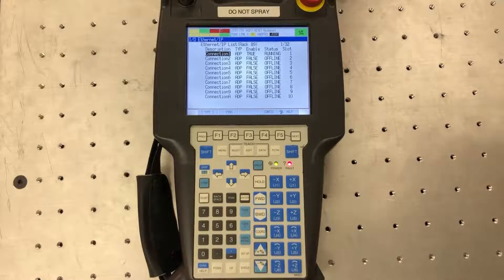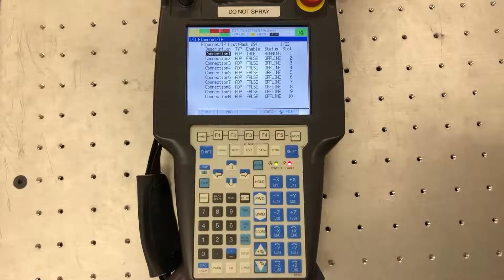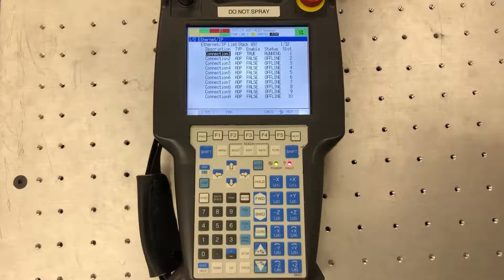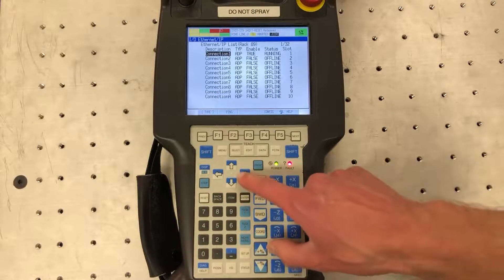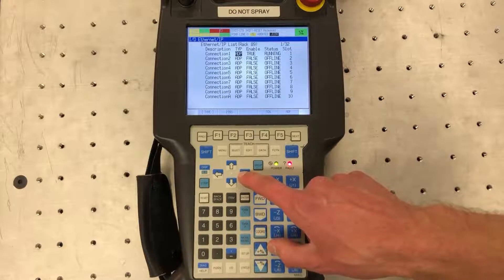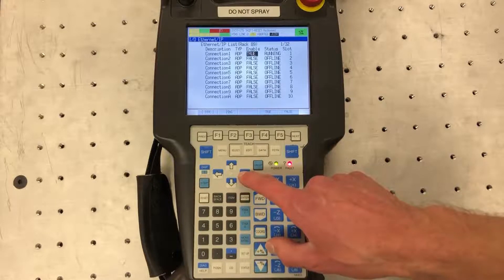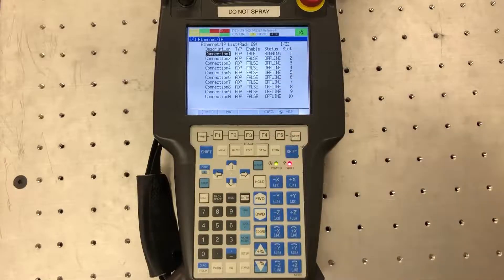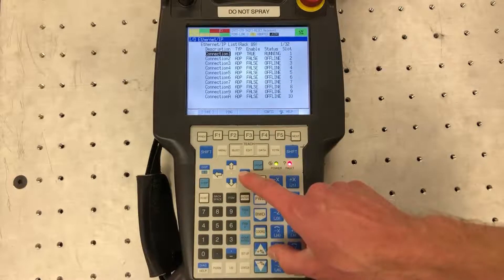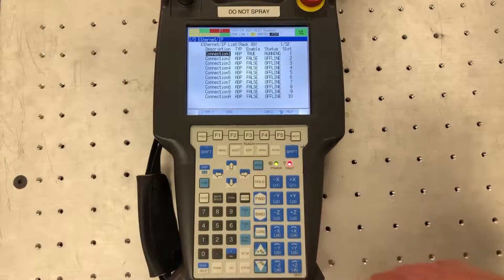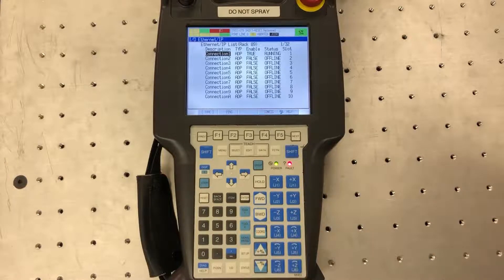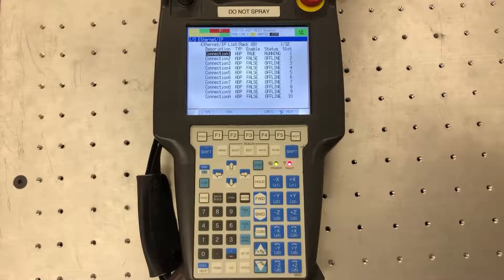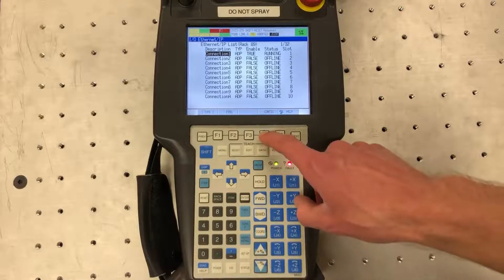Now you're going to have a list of different connections that you can have on your robot. In this case my first one I have an adapter. If you purchase the scanner option you can select this as a scanner rather than an adapter. In this case we'll continue with adapter and then you can enable it and this will say if it's running or not. In this case mine is running. To configure your adapter, when you first enter the screen it's going to show all of them as false and none of them will be running. You're going to hover over the one you want to use and you're going to hit F4 for config.